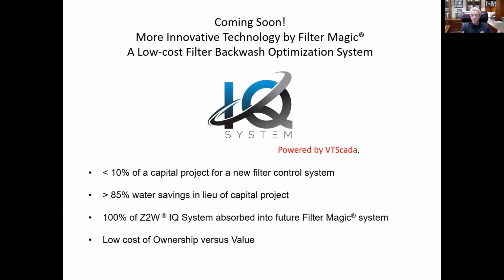It doesn't control the backwashes. What it does is monitor, analyze, and provide information to the client so they can use it to fine-tune whatever control system they have. They can take the knowledge, walk over to their consoles, adjust it, and over 2 or 3 backwashes using the IQ system, calibrate their backwash for 85% water savings or more.